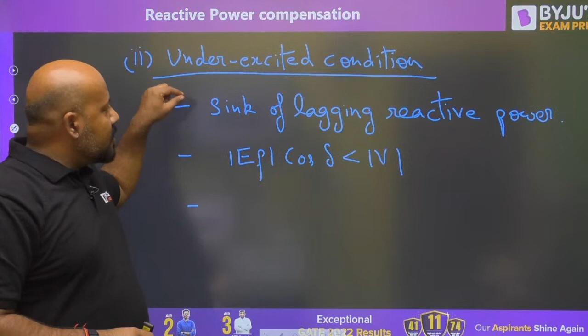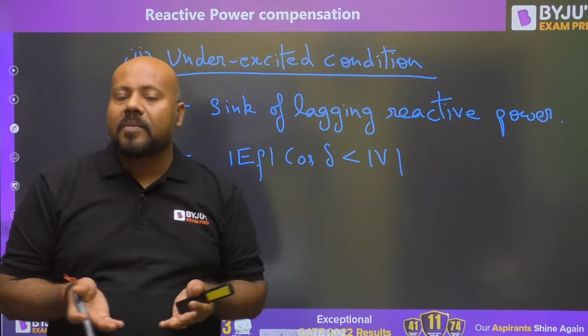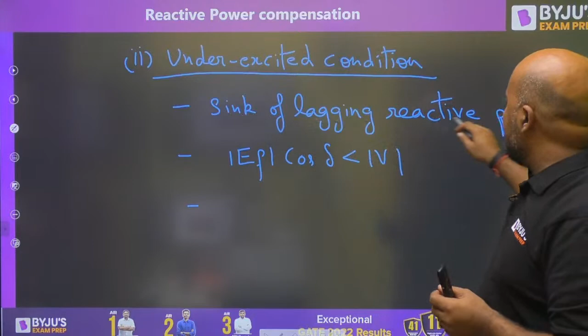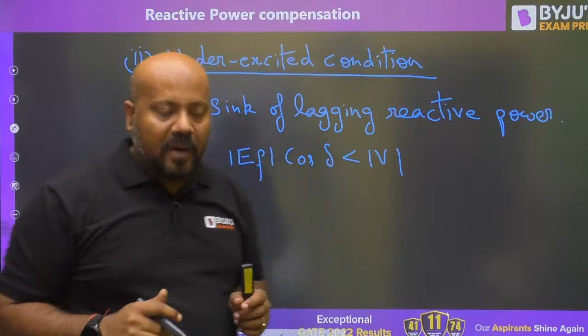The same logic you can apply here. If you are saying your generator is acting as a sink of lagging reactive power, it means you can say it is acting as a source of leading reactive power. I hope you are getting my point. If your basic nature is supplying power, you have to understand accordingly. Acting as a sink of lagging reactive power means actually you are supplying leading reactive power. So what is the operating power factor? Leading.